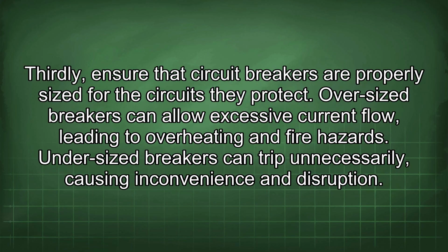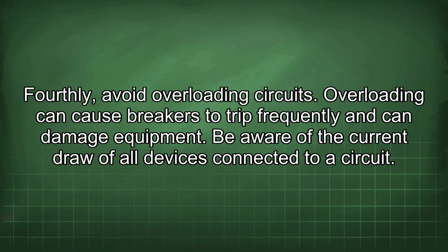Thirdly, ensure that circuit breakers are properly sized for the circuits they protect. Oversized breakers can allow excessive current flow, leading to overheating and fire hazards. Undersized breakers can trip unnecessarily, causing inconvenience and disruption. Fourthly, avoid overloading circuits. Overloading can cause breakers to trip frequently and can damage equipment.